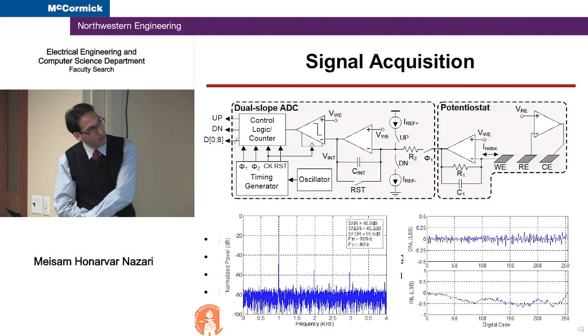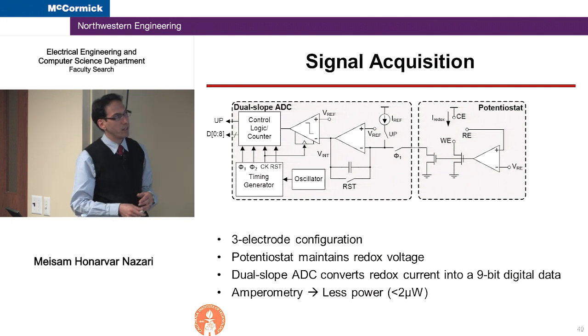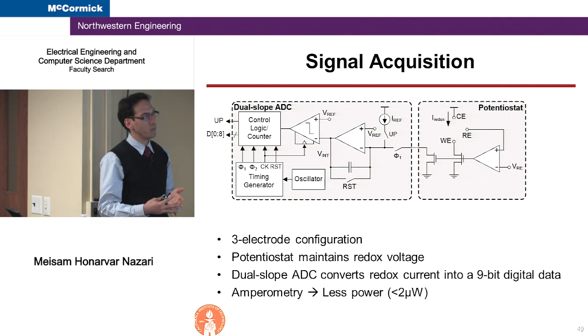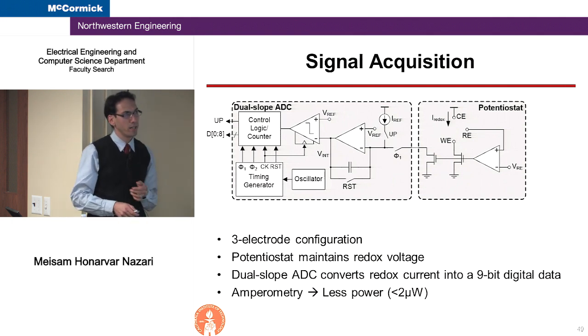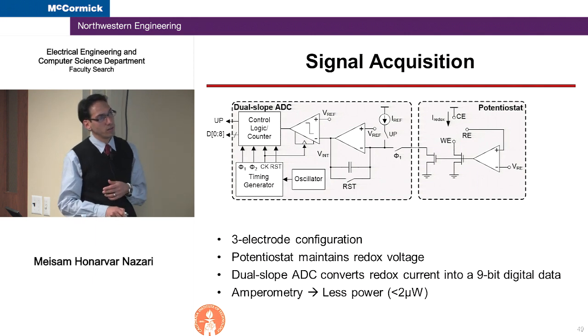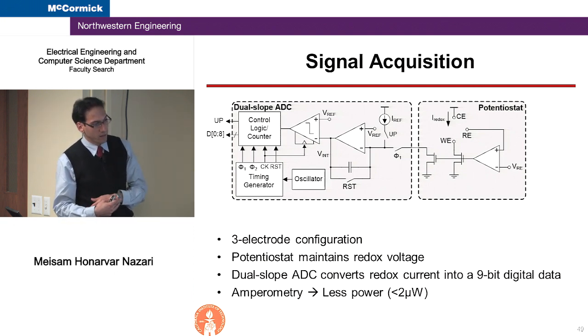So this system in total consumes less than 6 microwatt, but because we are very limited in power, in the next generation that we just recently submitted for fabrication, we changed the design so that we can reduce the power consumption. Of course, it's not going to be able to do cyclic voltammetry because it's unidirectional measurements. We can only do amperometry, but then this is similar to all other devices that do glucose monitoring.